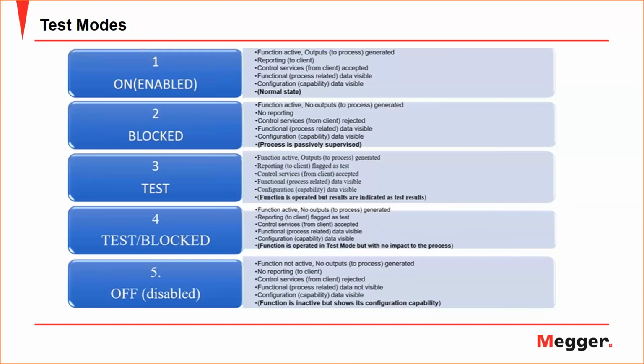That's why the standard introduced a new concept of testing mode. And this concept is that you put your IED in a test mode. There are, I would say, 5 levels, and it is required like this for many reasons. This test mode starts with the first mode being on or enabled, which is similar to the normal state, or I would say the in-service state for the IED. All the inputs will be processed, and then outputs will be generated based on the values. So it's like a live state for your IED.